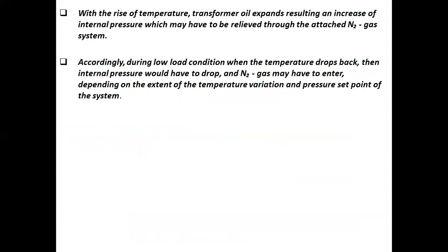Now, points to be noted. With the rise of temperature, transformer oil expands, resulting in an increase of internal pressure, which may have to be relieved through the attached nitrogen gas system. Accordingly, during low load condition, when the temperature drops back, the internal pressure would drop and nitrogen gas may have to enter, depending on the extent of the temperature variation and pressure set point of the system.